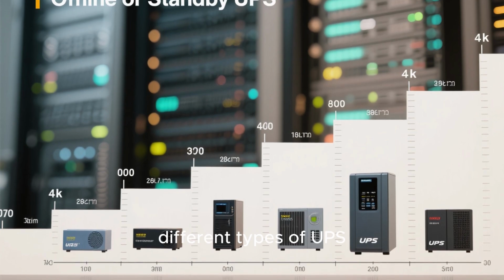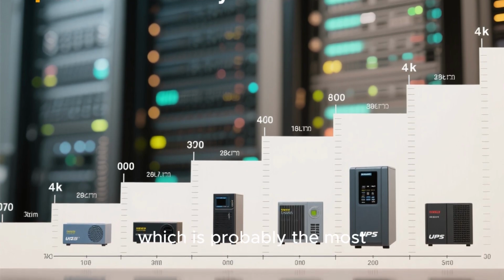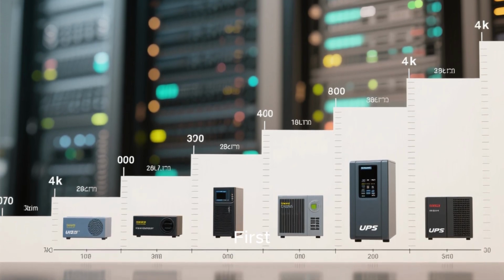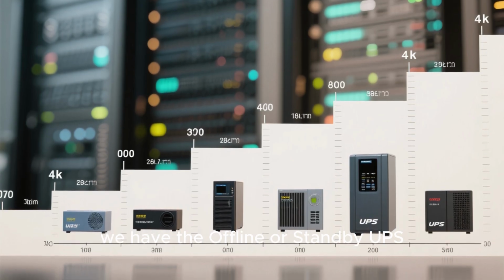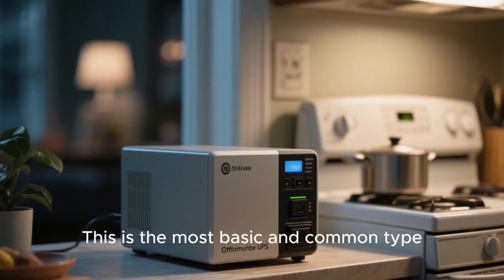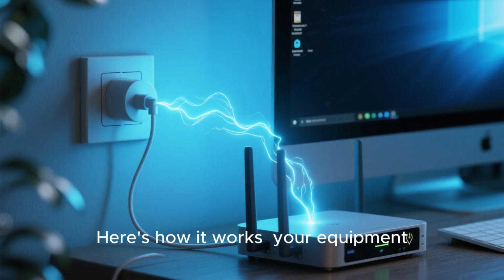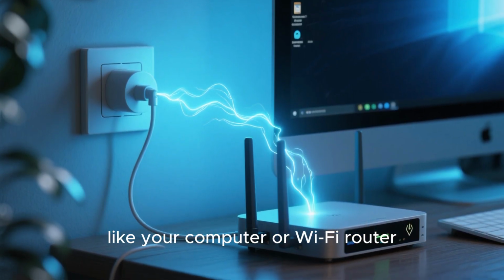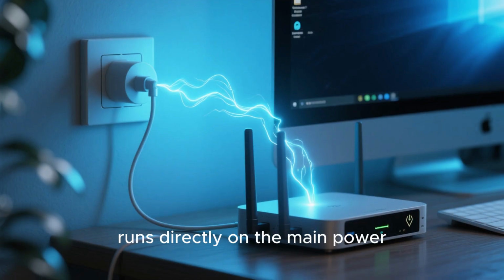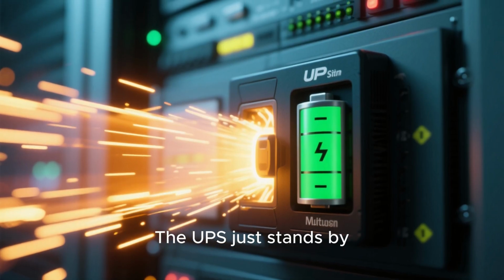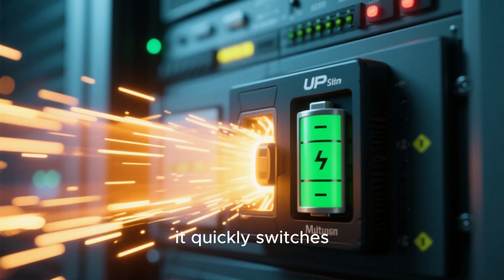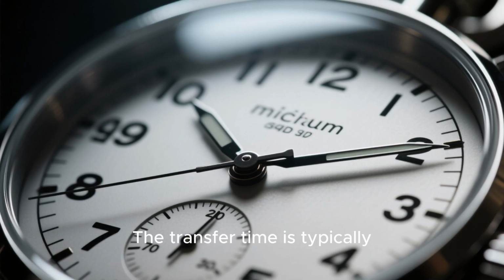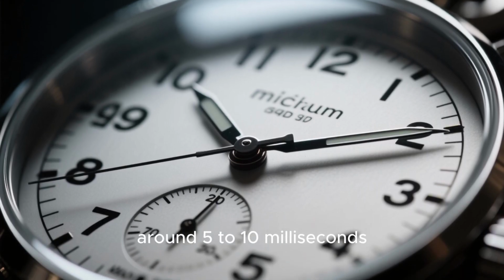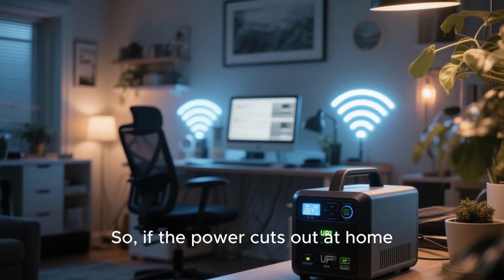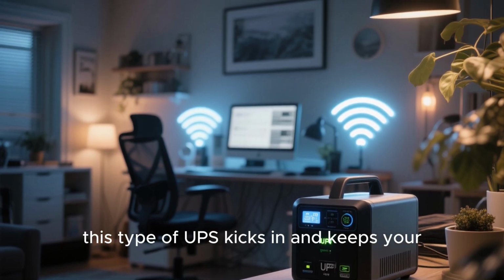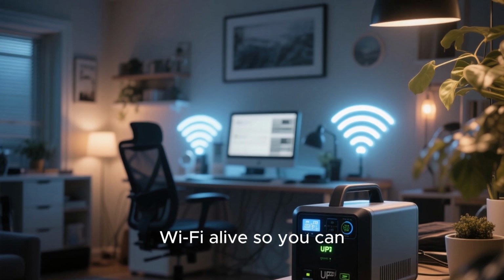This brings us to the different types of UPS, which is probably the most important part to understand. First, we have the offline or standby UPS. This is the most basic and common type you'll find for home use. Here's how it works. Your equipment, like your computer or Wi-Fi router, runs directly on the main power. The UPS just stands by. When it detects a power failure, it quickly switches over to its internal battery. The transfer time is typically around 5 to 10 milliseconds. So, if the power cuts out at home, this type of UPS kicks in and keeps your Wi-Fi alive so you can finish your work.